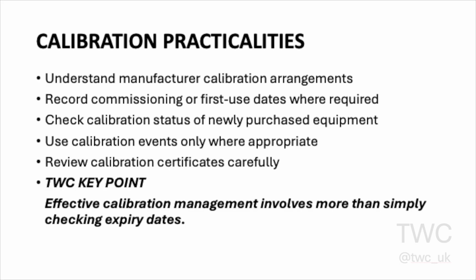Some installers also make use of calibration days organised by manufacturers, wholesalers or calibration providers. These events can be convenient and may sometimes be offered free of charge or at a reduced cost. However, calibration events should only be used where appropriate and should not result in calibration intervals being exceeded while waiting for a future event. The important point is to understand exactly what the calibration documentation is telling you and how the equipment should be managed.